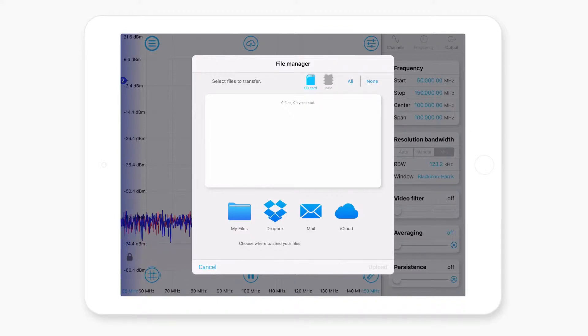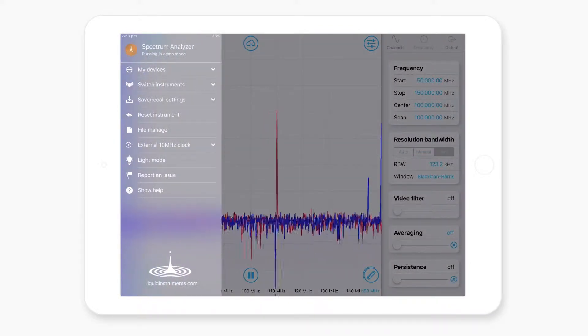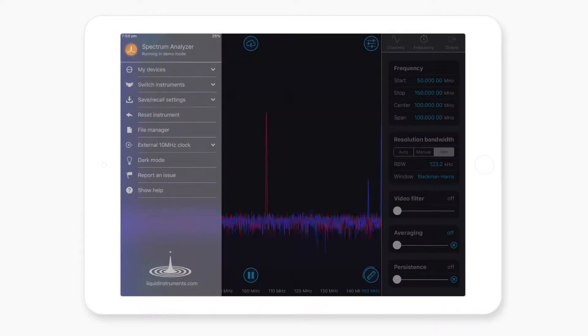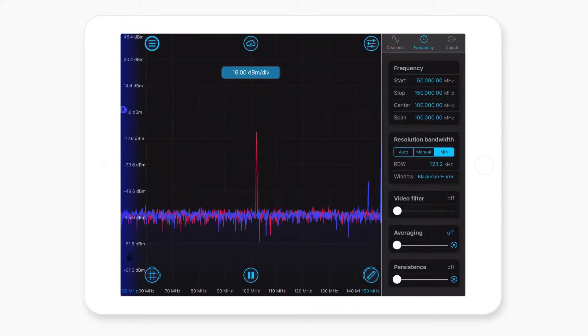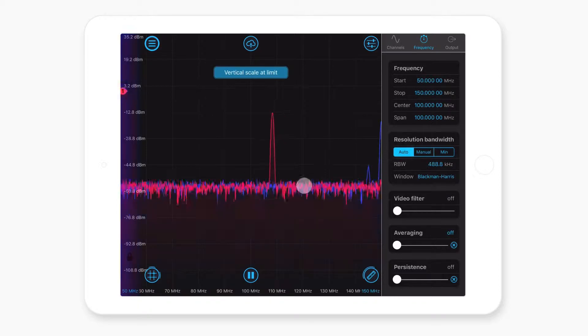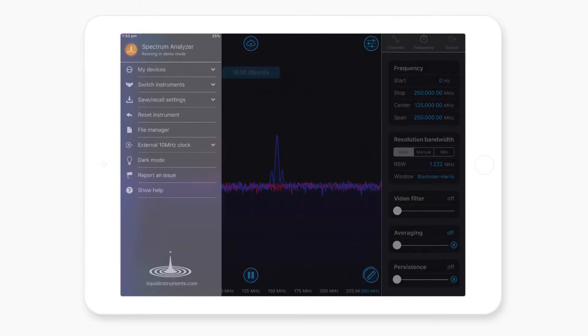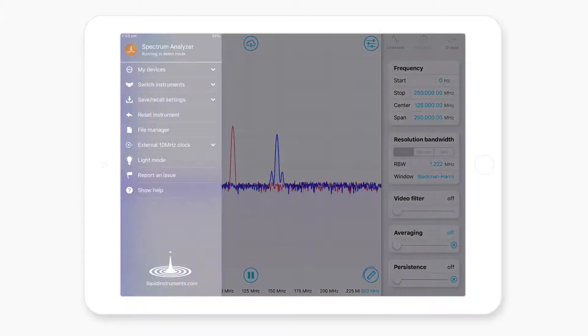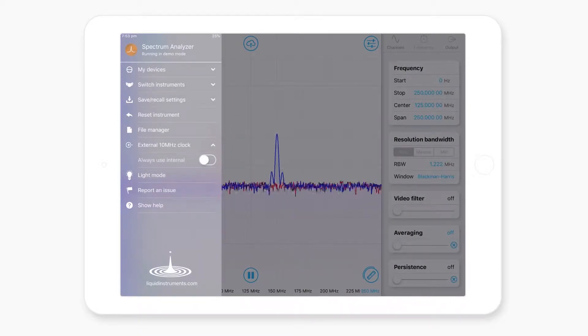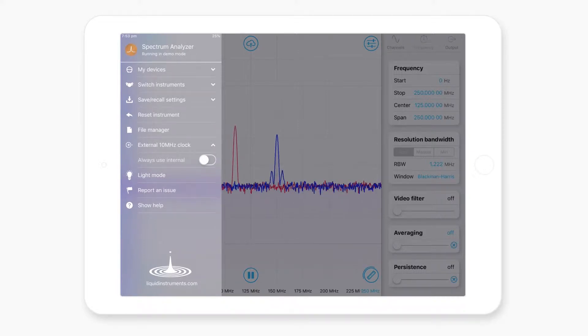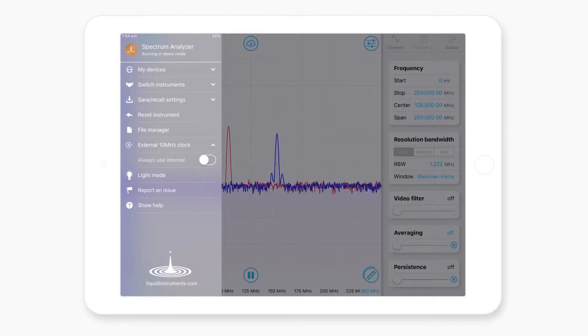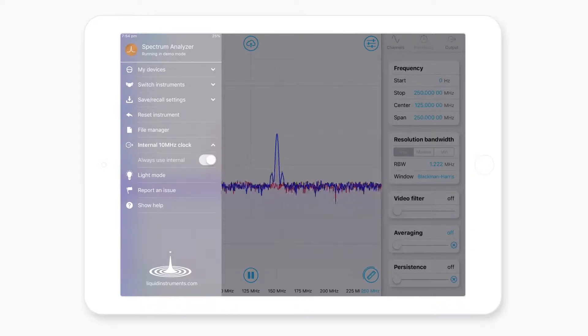You can also access files. So this is useful if you've saved a whole bunch of data and you want to basically manage it all. And then you've also got things like changing light mode. So if you work in a dark lab, this is a lifesaver because you won't go blind. But most of the time people will just want to use it on light mode because it looks pretty cool. And also things like external 10 megahertz reference clock. So this is important because if you connect an external 10 megahertz reference to MokuLab, it'll automatically detect that. It'll phase lock to that reference. But if you didn't want it to do that for any reason, you can force it to use the internal clock.